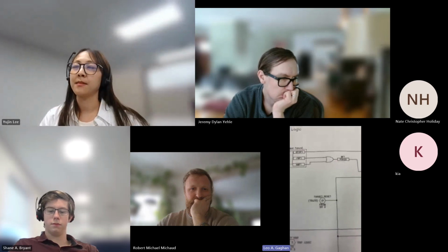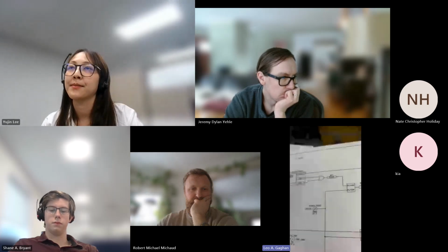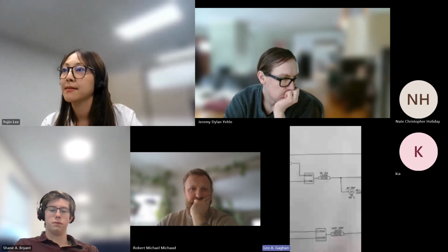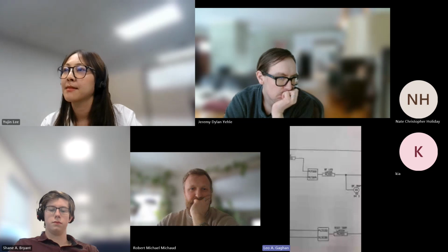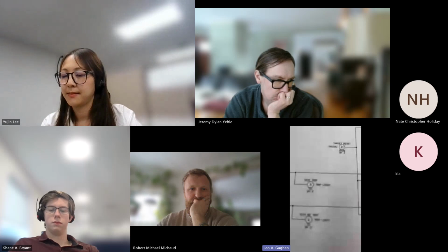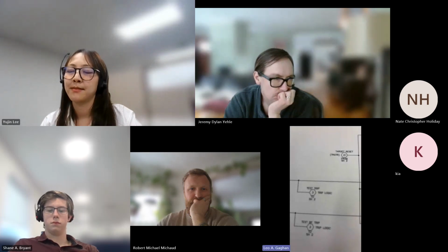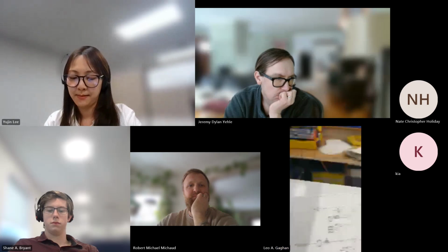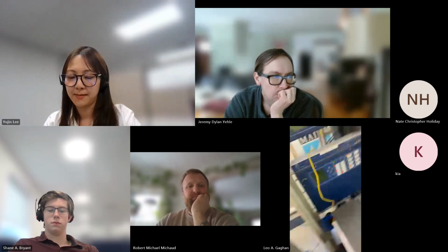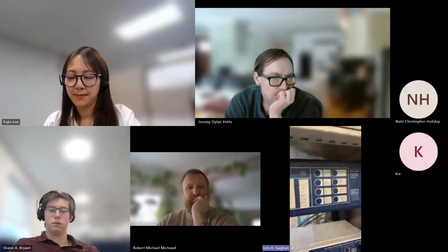Which if you guys have the PDF right there, you can look right over there. You should see the test trip coming in. It'll hit the trip equation. The trip will then go to the output, and then we'll have an indication on the front of the relay here. So right now, breaker's closed. All right, we can see the breaker's closed.